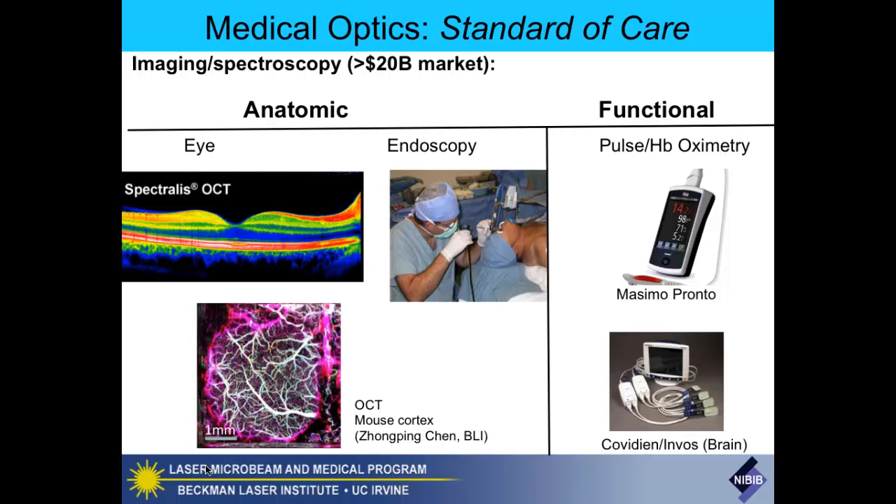These are anatomic approaches; these are functional techniques. With these functional techniques, based on pulse and hemoglobin oximetry, there's a huge amount of activity in this area. They're not looking at anatomic structure—they're looking at functional change in tissue. They're spectroscopic based methods. A beautiful example is the PRONTO system from Masimo, a small bedside multi-wavelength spectroscopy instrument able to recover hemoglobin non-invasively from a patient.